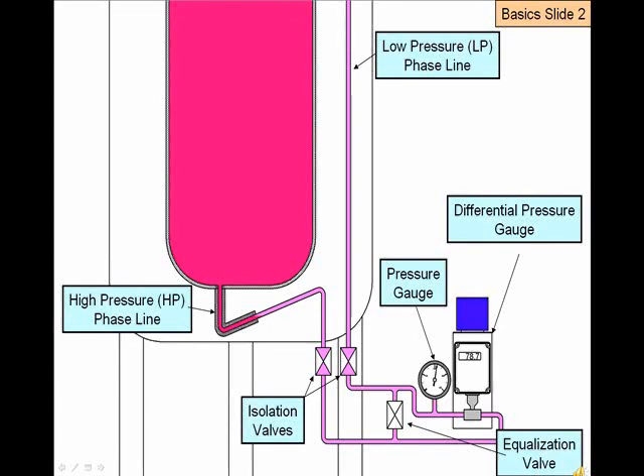The equalization valve, when open, creates a bypass between the HP line and LP line, resulting in no differential condition. This can be used to check the zero of the differential gauge.